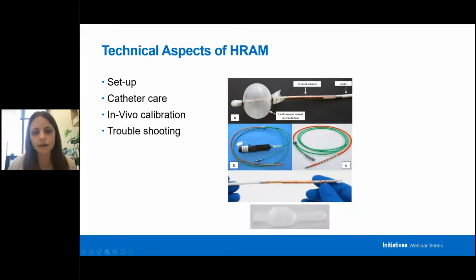Another way we take care of these is we recommend doing a weekly bath for the catheter, essentially called in vivo calibration. The goal is for the sensors to adapt to and recognize human body temperature. You let the catheters sit in body temp equivalent water, about 96.8 to 100.4 degrees Fahrenheit, for 1 minute every 5 to 7 days so the sensors can continue to recognize that. It's a little spa day for them.